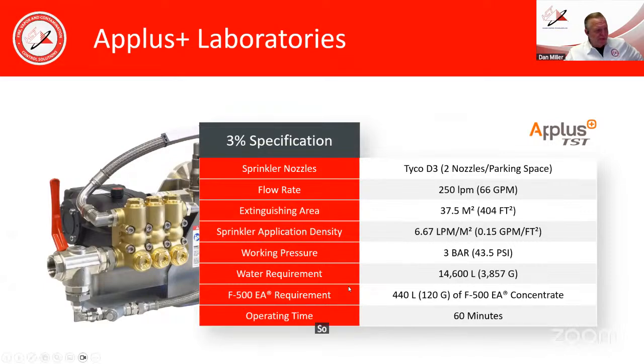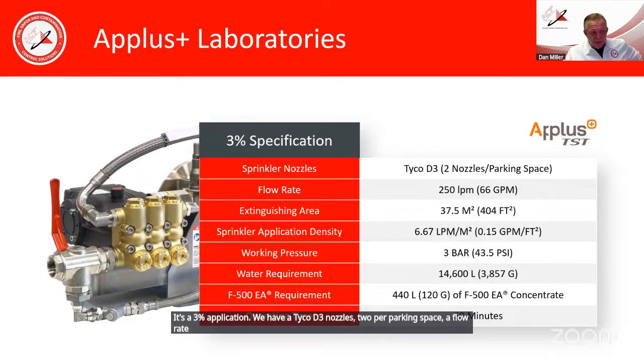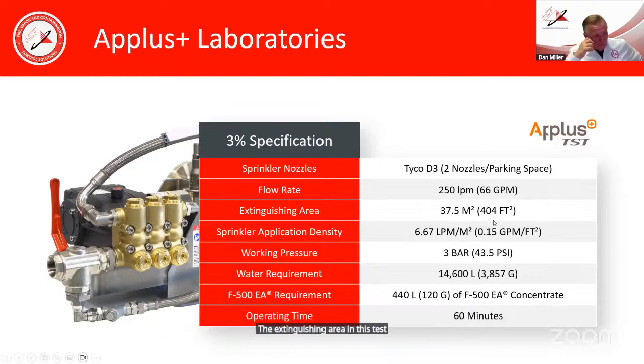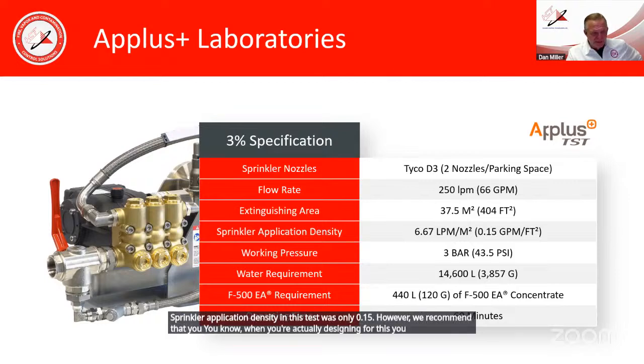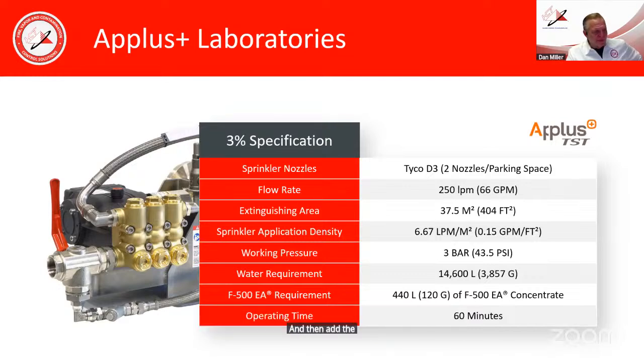So if you look at some of the components that are involved in this system, it's a 3% application. We have Tyco D3 nozzles, 2 per parking space, a flow rate of 250 liters per minute, or only 66 gallons per minute. The extinguishing area in this test was 404 square feet, or 37.5 square meters. Sprinkler application density in this test was only 0.15. However, we recommend that when you're actually designing for this, you design the system to either the NFPA or FM requirements, and then add the F500 at 3% because it'll more than do the job.